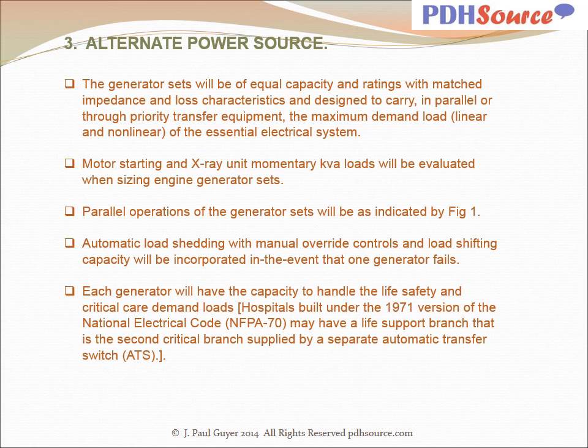Automatic load shedding with manual override controls and load shifting capacity will be incorporated in the event that one generator fails. Each generator will have the capacity to handle the life safety and critical care demand loads. Hospitals built under the 1971 version of the National Electrical Code, NFPA 70, may have a life support branch that is the second critical branch supplied by a separate automatic transfer switch, abbreviated ATS.